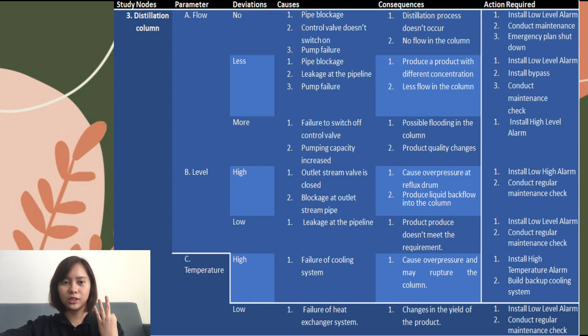As for temperature, high temperature would mean failure of the cooling system, and it would cause overpressure and may rupture the tank, and therefore we have to install a high temperature alarm and build a backup cooling system. As for low temperature, it would be caused by failure of the heat exchanger system, which would also cause changes in the yield of the product, and it is required to install a low level alarm and conduct regular maintenance. In this PID also, there are 3 distillation columns, which apply the same hazard analysis because they have the same process.